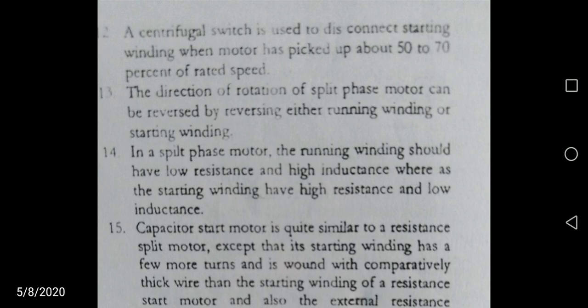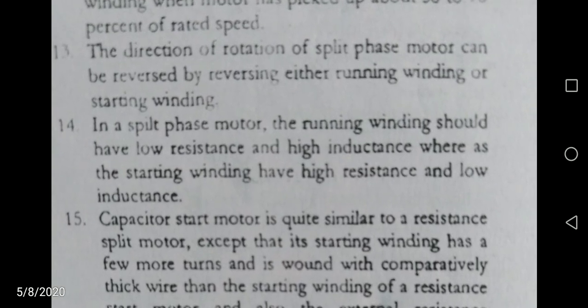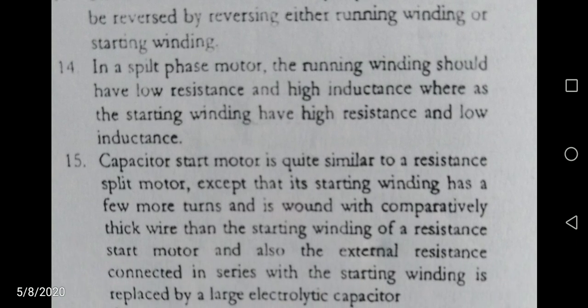The direction of rotation of a split phase motor can be reversed by reversing either the running winding or the starting winding, but not both. In a split phase motor, the running winding should have low resistance and high inductance, whereas the starting winding has high resistance and low inductance.